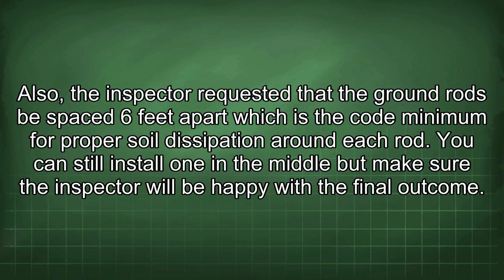hazards. Also, the inspector requested that the ground rods be spaced 6 feet apart, which is the code minimum for proper soil dissipation around each rod. You can still install one in the middle, but make sure the inspector will be happy with the final outcome.